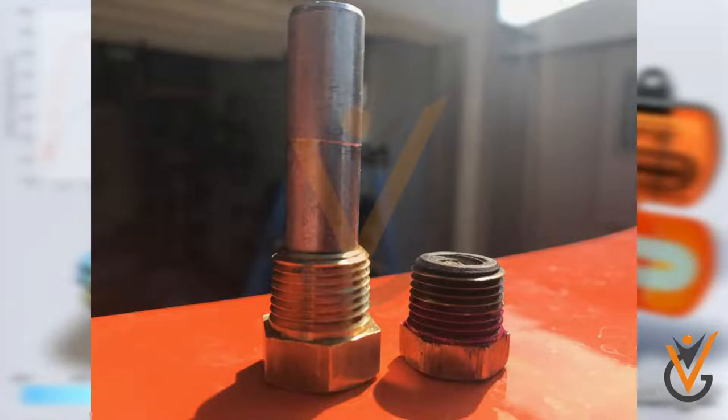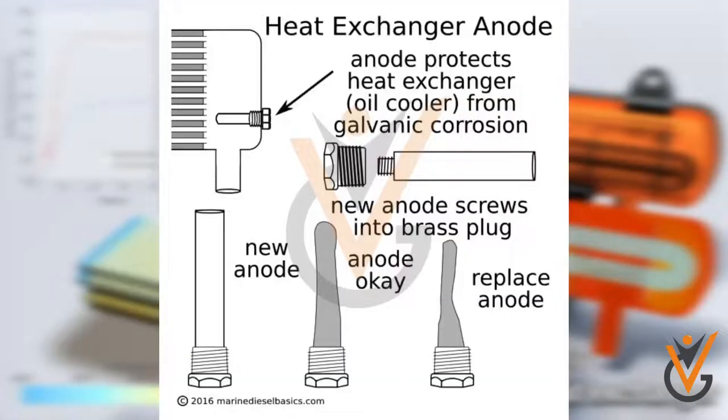Sacrificial anodes are provided to avoid corrosion of the heat exchanger. Soft iron or mild steel anodes can be fitted in the water boxes, and provided they cause no turbulence, they will provide cathodic protection and a protective film.